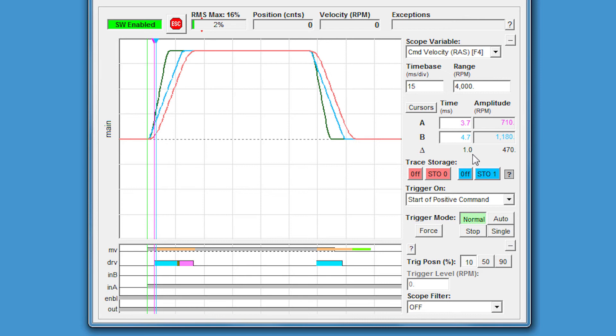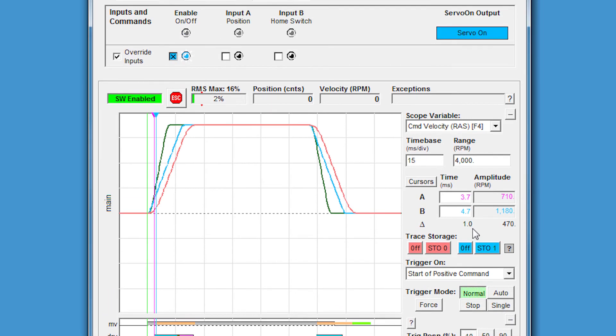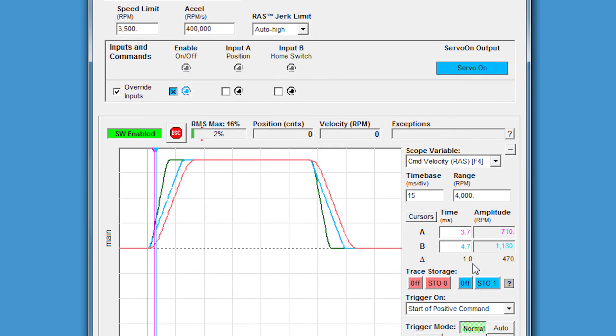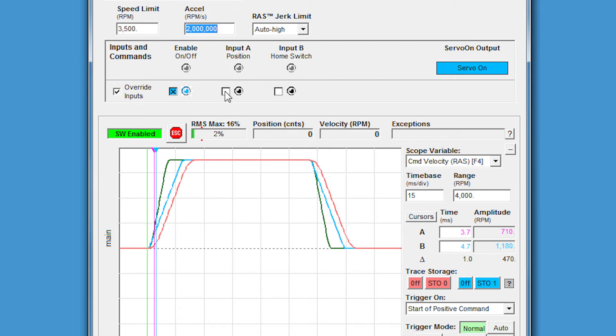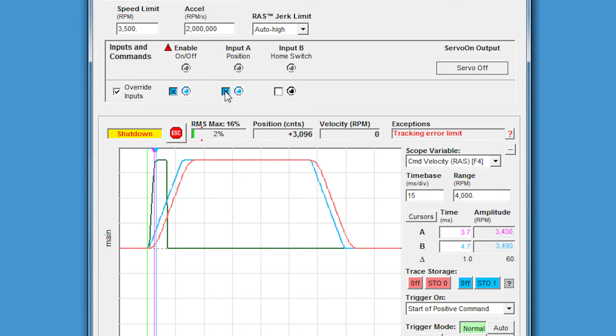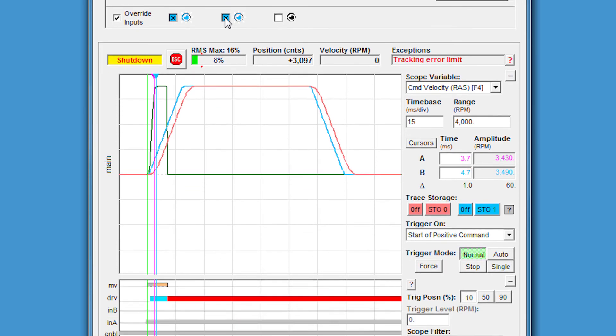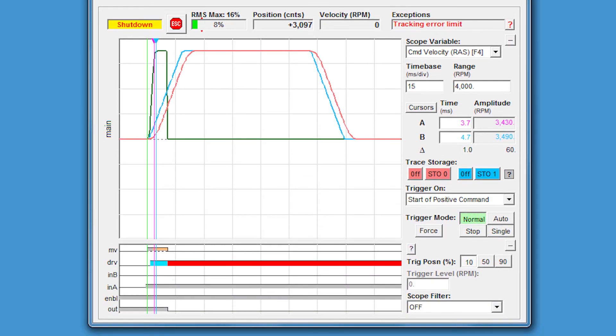What would happen if we even increase the acceleration rate even faster? Let's say 2 million RPM per second. Let's do that and see what impact it has on the move. The motor shut down for some reason. It looks like in the drive status we have a red light, which we didn't come across before.